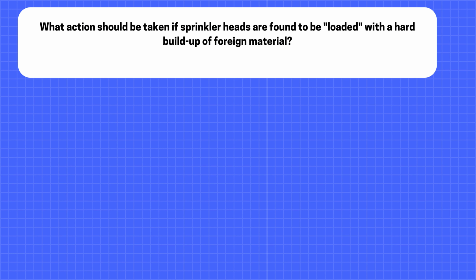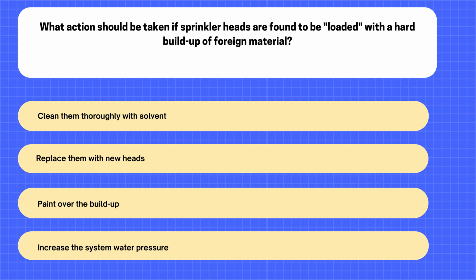What action should be taken if sprinkler heads are found to be loaded with a hard buildup of foreign material? A. Clean them thoroughly with solvent. B. Replace them with new heads. C. Paint over the buildup. D. Increase the system water pressure.